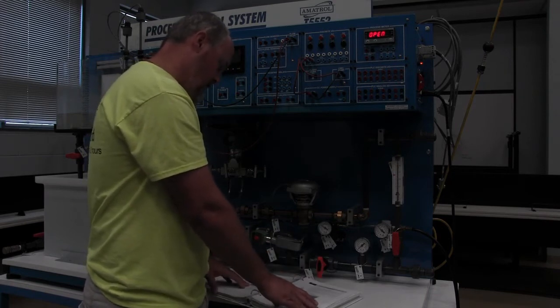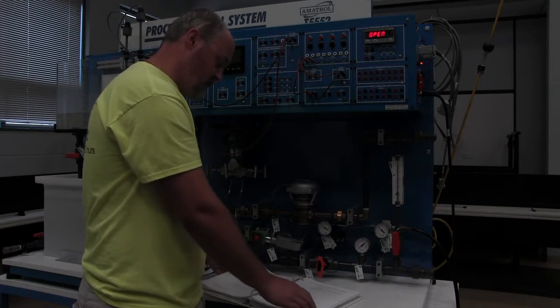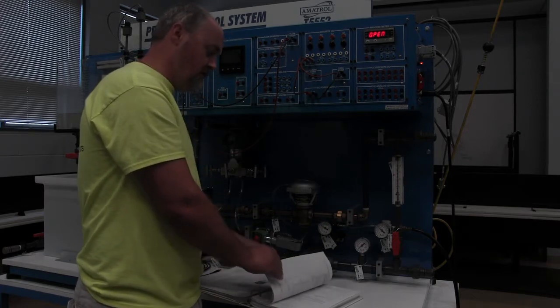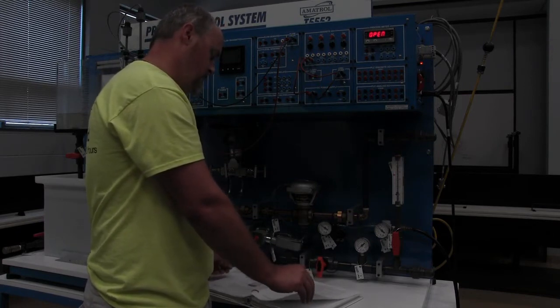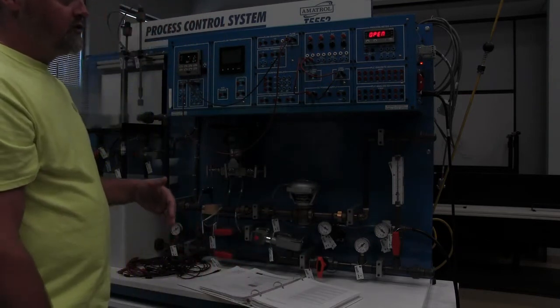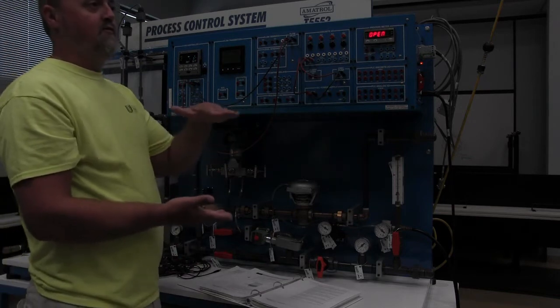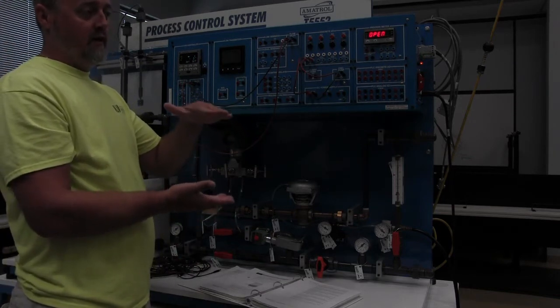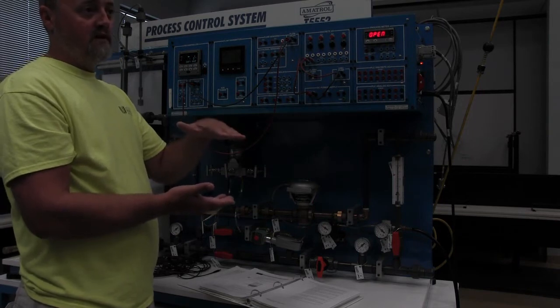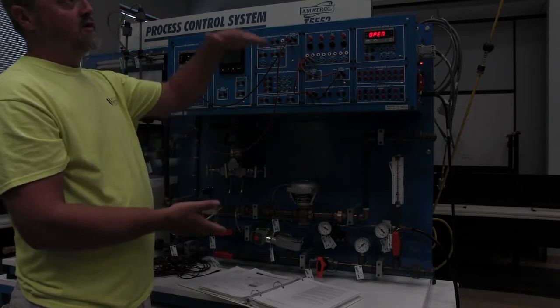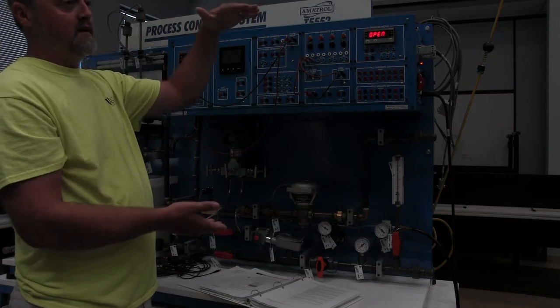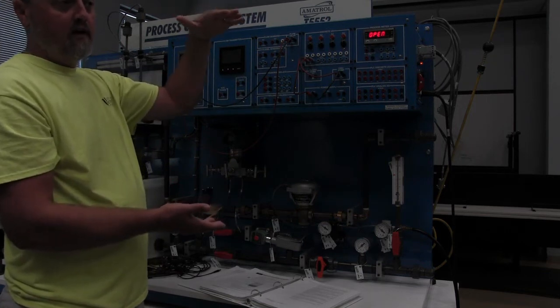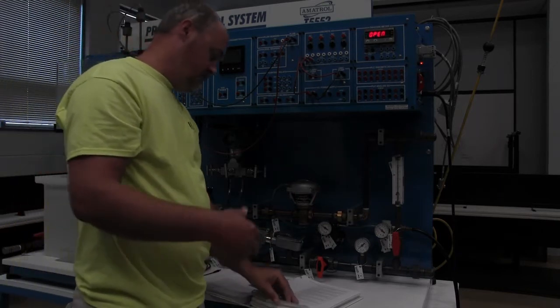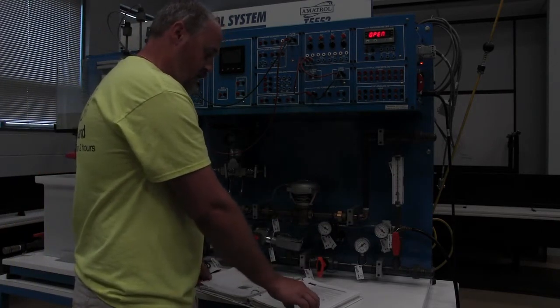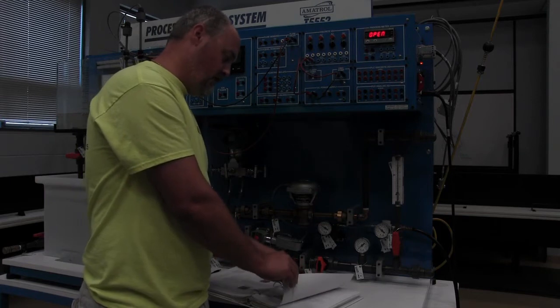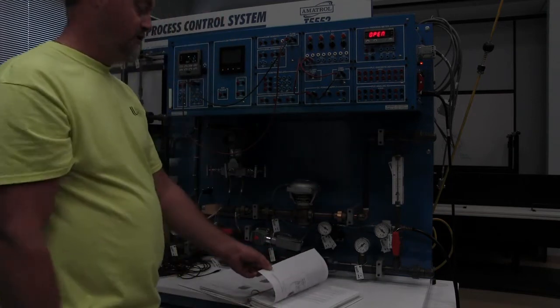So this is converting pressure into a level. When you convert pressure into a level, the formula you're going to use is 2.31. So for every 2.31 feet that you have of a liquid level column, you have 1 psi. So at 231 feet, you're going to have 100 psi. So anything you need to convert from level into pressure, you would use the formula of 2.31, and that's going to give you your pressure.